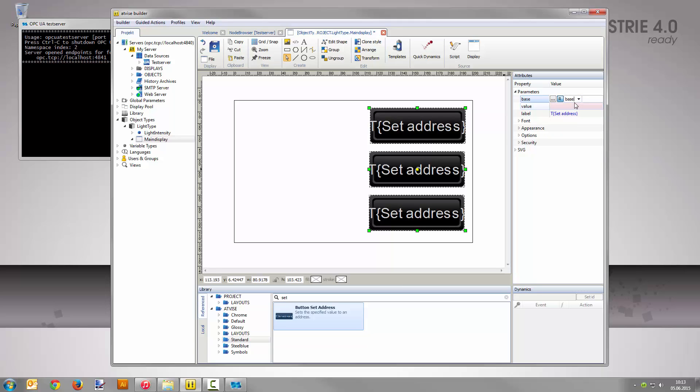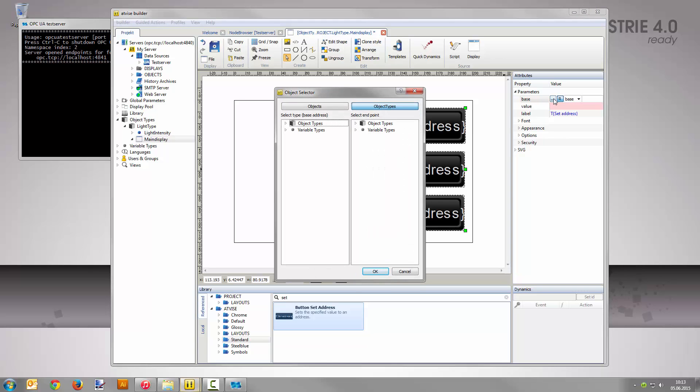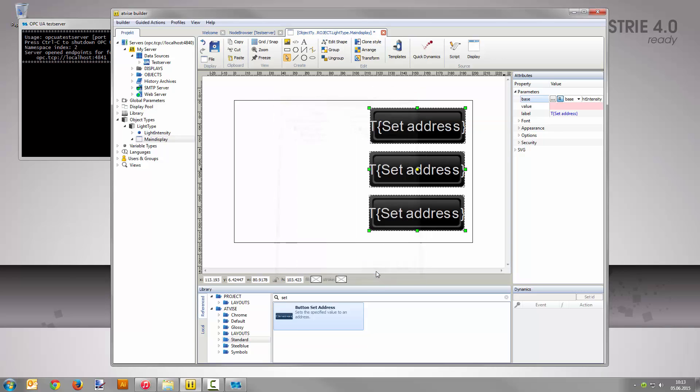Relative addressing ensures that the node address is relative to its base instance which will be created later on. Now click the button with the three dots on it to select a node address. Expand object types in the left column and select light type as base address. As endpoint, select the node light intensity in the right column. Save your selection with OK and confirm your input in the parameter's value field by pressing the enter key.